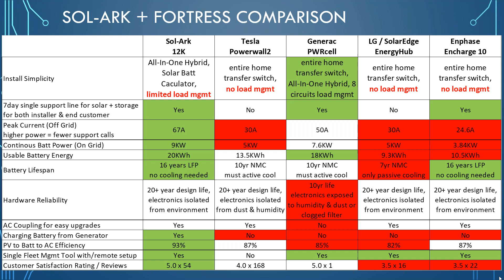The last thing I want to point out is efficiency. Our PV to battery to AC efficiency is at 93%, and a lot of the others are a lot less efficient. The main reason is we have fewer conversions—it's a transformerless design, so we don't convert as many times as a lot of these other AC coupled applications. Most of these other guys go DC, AC, AC, back to DC, DC to AC again, whereas we just go DC, DC, DC, AC. We cut out a whole step, saving quite a bit in efficiency. That means you need fewer panels and less battery, but you can always have more capacity in the battery you have as a result.